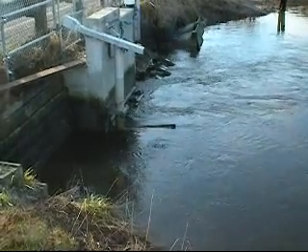My new control mechanism works great at this site and in fact will work at virtually any site. The retrofitted gate opens wide on every falling tide when the water levels are equal. It allows limited backflow on the rising tide, and it closes reliably when the water level in the slough upstream reaches the desired water level, plus or minus about 4 inches.